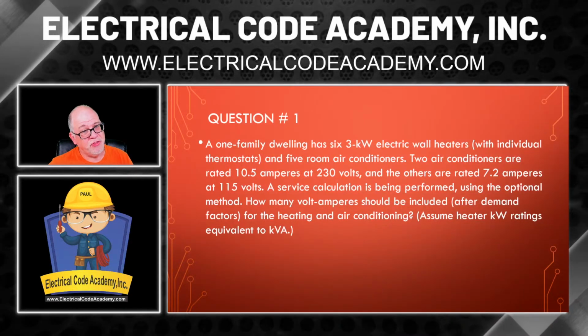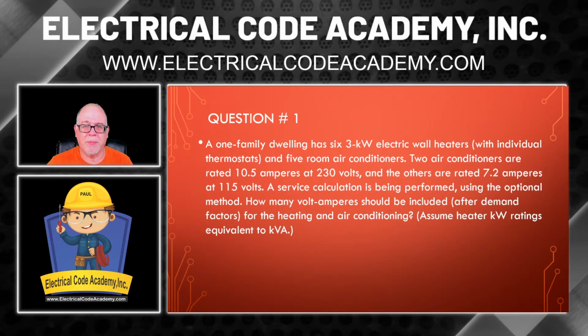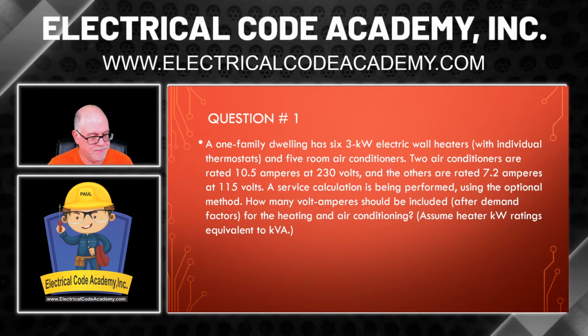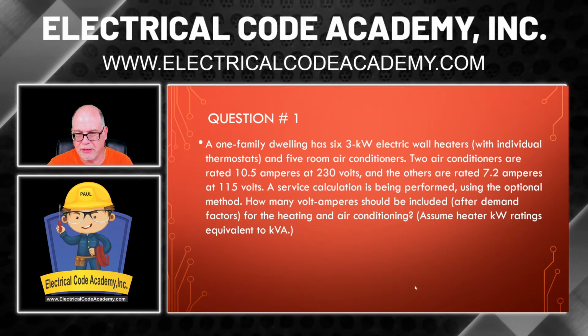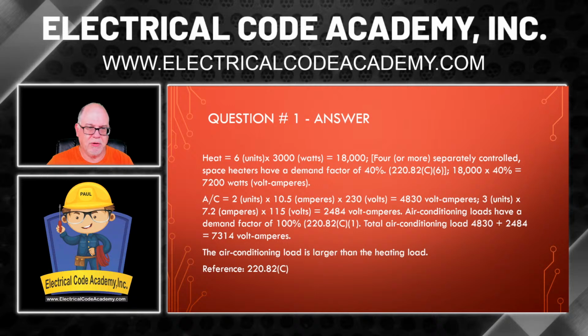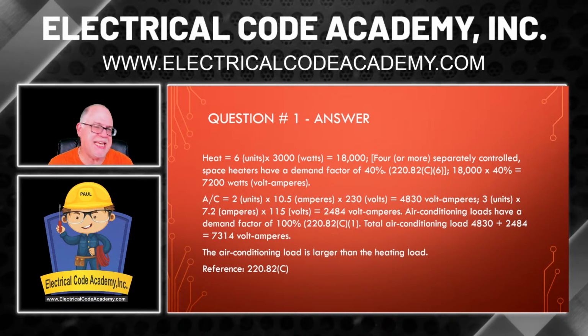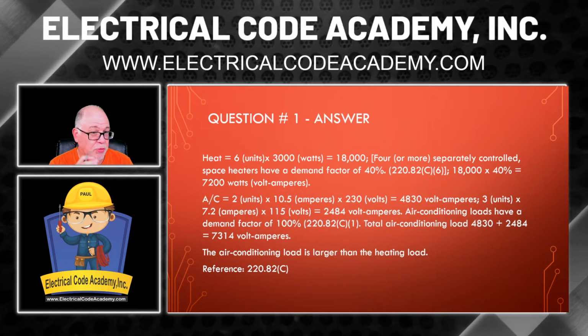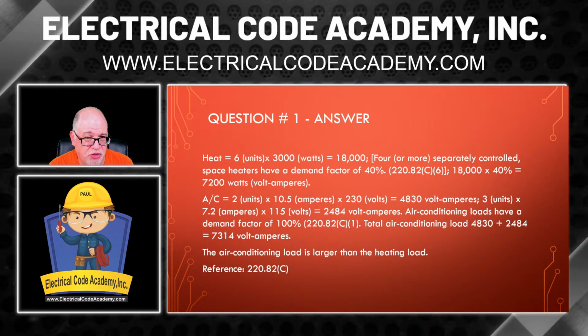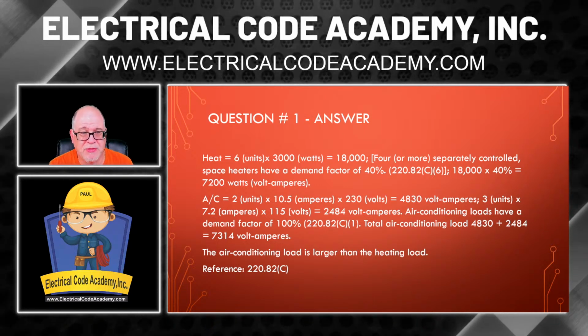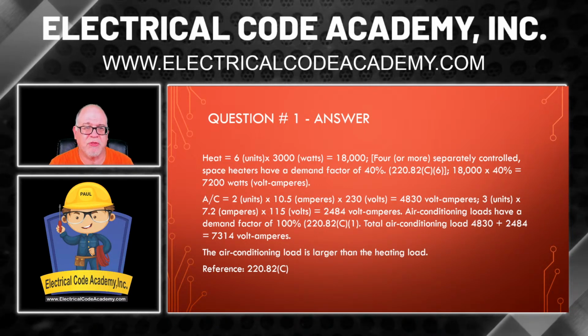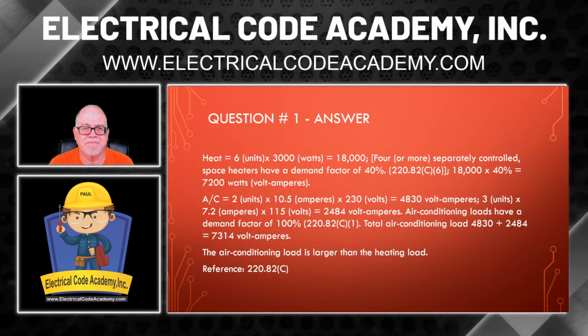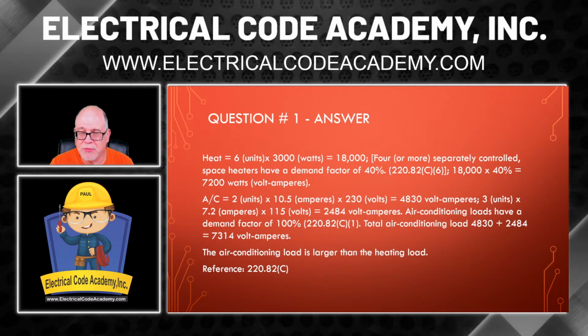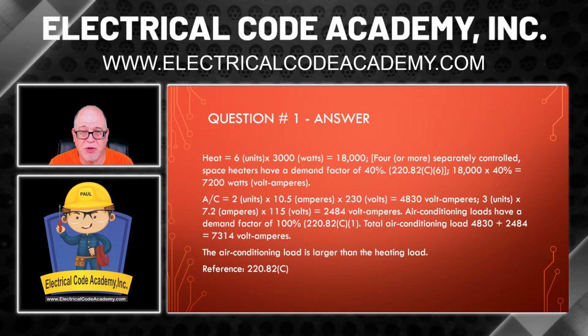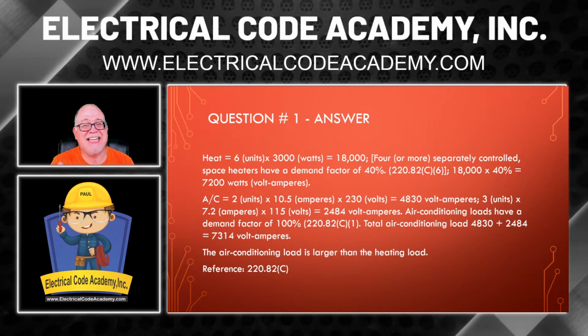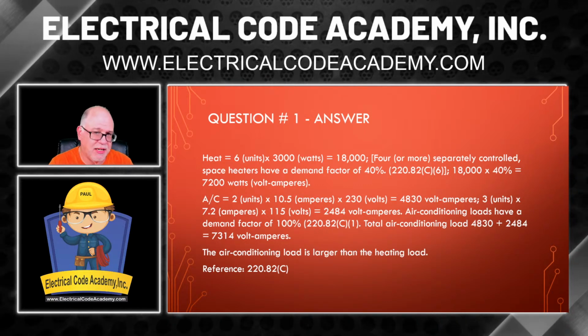So here was our question, and we got to do a couple things in order to get there. All right, let's go on and start working the math. First thing, let's knock that heat out. There were 6 of them, 3,000 watts each, or 3 kW each. So we're going to work this out: 6 times 3,000, or 6 times 3 kW, equals 18 kW. But in this case, it's 18,000, the way we're working it out here.